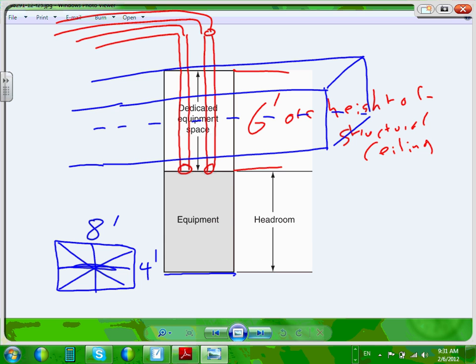So in this dedicated space, though, the area above the dedicated space shall be permitted to contain fire protection. A sprinkler system shall be permitted for dedicated space. If you have a sprinkler system just dedicated for the switchgear, right above the switchgear, if there's fire on the switchgear, they don't open unless there's a fire. They allow you to have a sprinkler system because that's fire protection. A suspended ceiling like this can enter this space, no problem. Suspended ceiling, sprinkler system, fire protection systems. If you have right above the area here.